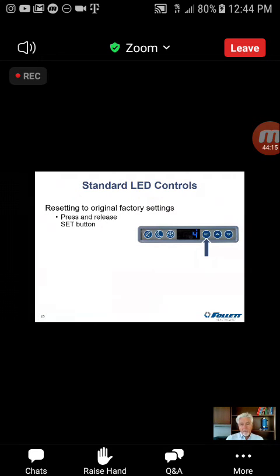So that's the min-max, it records those highs. What you may have noticed is that when we display the peak high temperature, it said 73 degrees. This relates to startup. One of the things that's important to keep in mind when you're starting up a new unit, the moment you plug that unit in, it is going to record whatever temperature is inside that cabinet, room temperature, as the peak high. So part of the startup should be someone needs to go back an hour or so later after that unit has had time to stabilize, and that value should be reset. And that way we have a meaningful peak high and peak low record of the cabinet temperatures inside that unit.